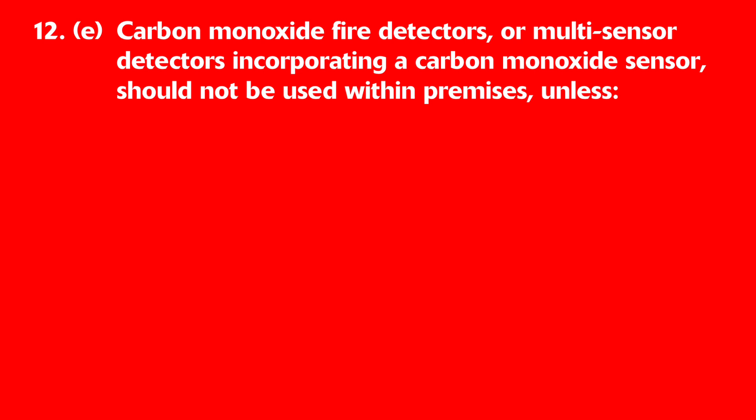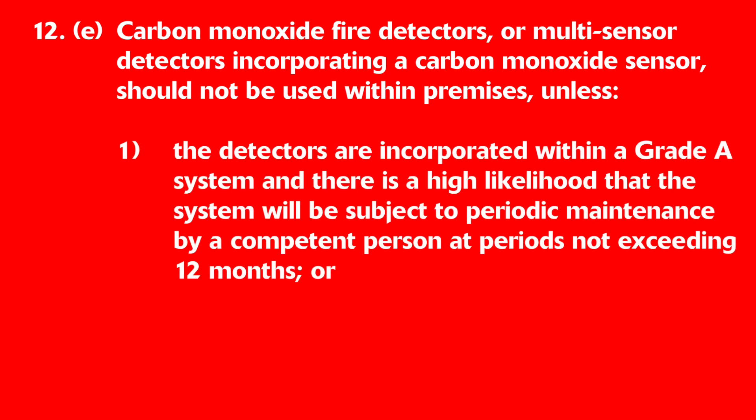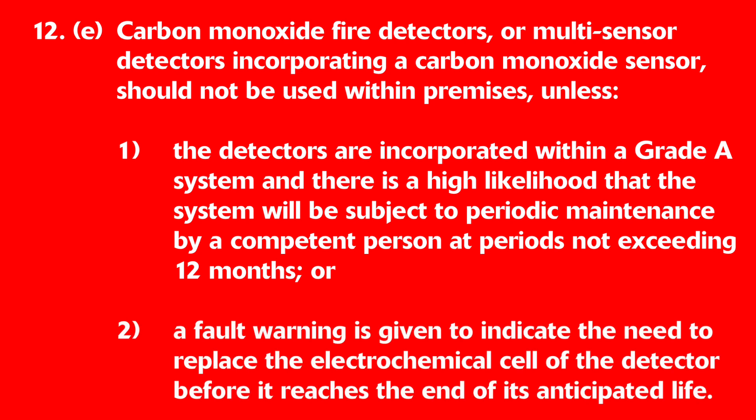The other type mentioned in the NIC Snags and Solutions book is the carbon monoxide fire detector. These operate differently to carbon monoxide warning detectors and will detect CO from smouldering fires and fires where the rate of burning is controlled by air supply. However, BS 5839-6 clause 12e states that carbon monoxide fire detectors, or multi-sensor detectors incorporating a CO sensor, should not be used unless incorporated within a grade A system and subject to periodic maintenance by a competent person at periods not exceeding 12 months, or a fault warning is given to indicate the need to replace the electrochemical cell before it reaches the end of its anticipated life. The CO detectors from BG Electrical are warning detectors rather than fire detectors, so they would never be used in place of a smoke detector. Reassuringly, they do have an end-of-life fault warning and are suitable for detecting CO from faulty fuel-burning appliances.